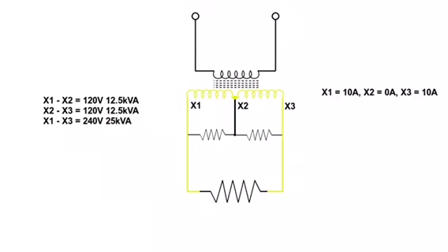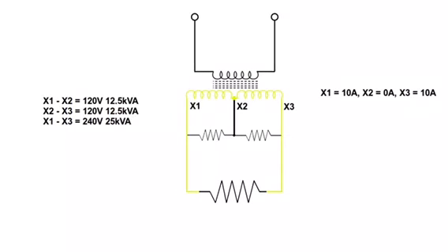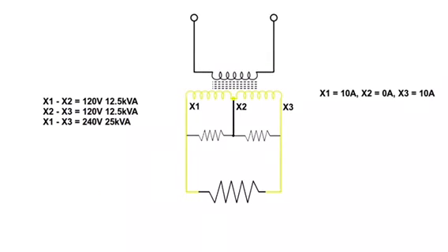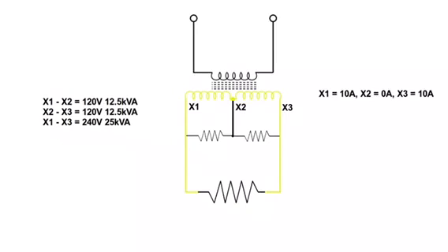Alright, I've added the second 120 volt load back to the system now. So the transformer in this configuration sees a total of one 240 volt load that is pulling 10 amps. This is no different from our first drawing. We have the 120 volt load plus the 120 volt load, which equals 240 volts. If we go across terminal X1, we will see 10 amps. If we hook on to terminal X2, we will see 0 amps. And if we hook on to terminal X3, we will see 10 amps.